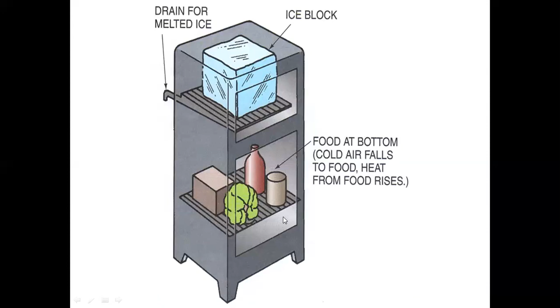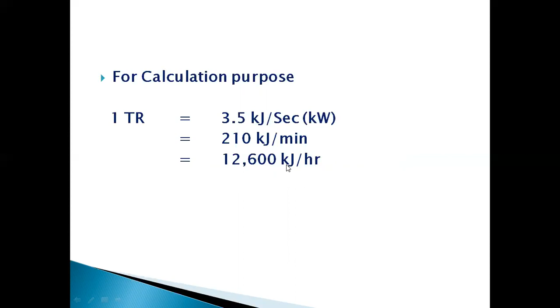Practically, for the purpose of calculations, there are some constant values. 1 ton of refrigeration equals 3.5 kilojoules per second. The meaning of this value is that if you fix a 1 ton AC in your bedroom, let us say, that AC in 1 second will remove 3.5 kilojoules of heat. In 1 minute, it will remove 210 kilojoules of heat. In 1 hour, if your 1 ton AC is working, it will remove 12,600 kilojoules of heat from this room. That is the meaning of 1 ton of AC.